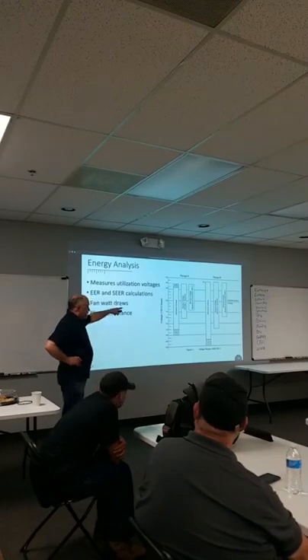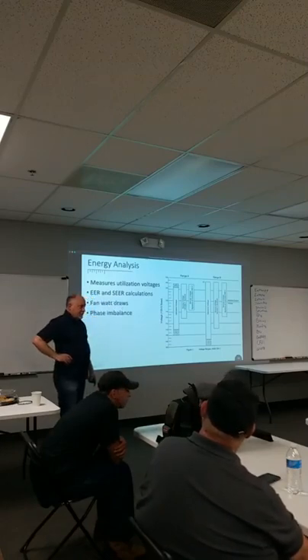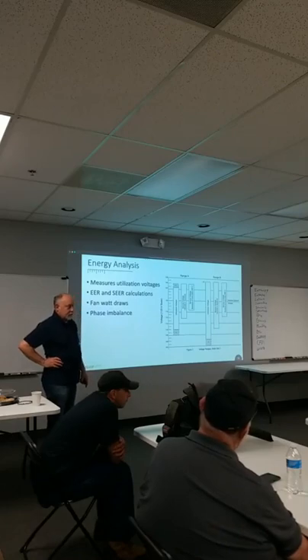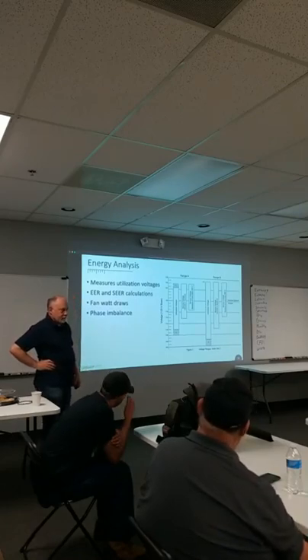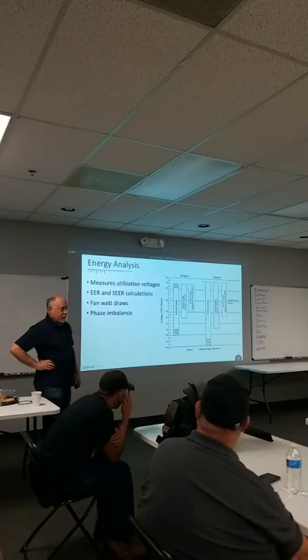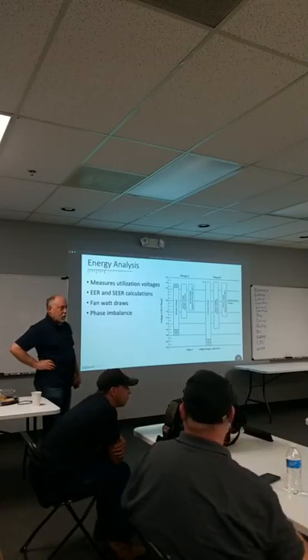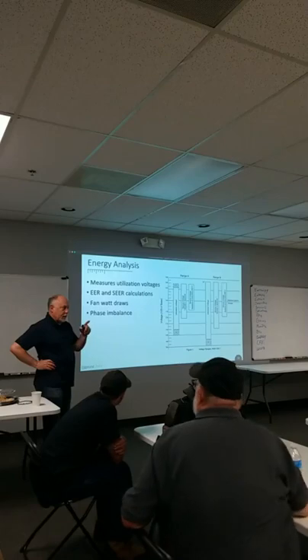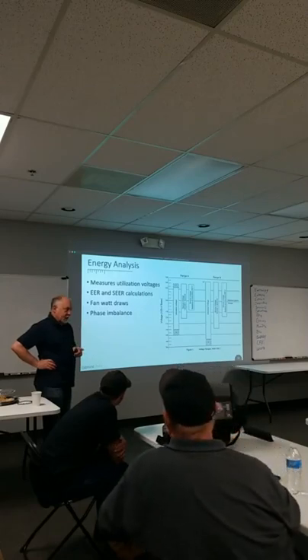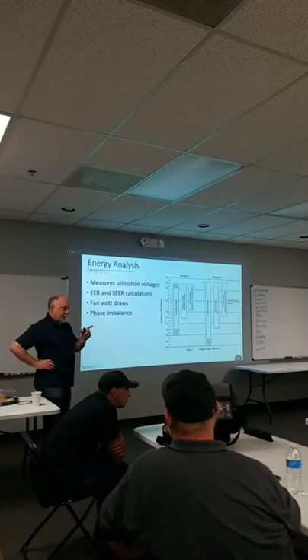Well, there's two different things. One of them is what the electric company is guaranteed to do with PUCO. That's plus or minus 5%. The motors, a lot of the time, plus or minus 10%. But your allowable voltage drop, if you size your conductors properly, you have a design drop, and then your voltage drop in service, your branch circuit, that you would consider when you're designing your wiring.